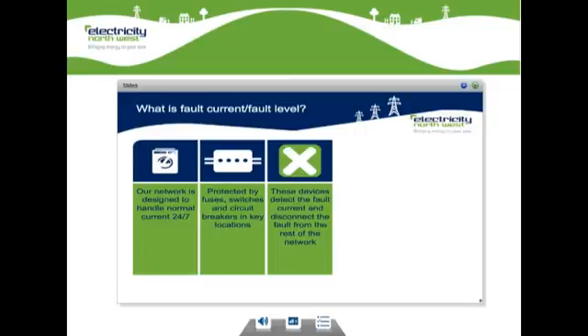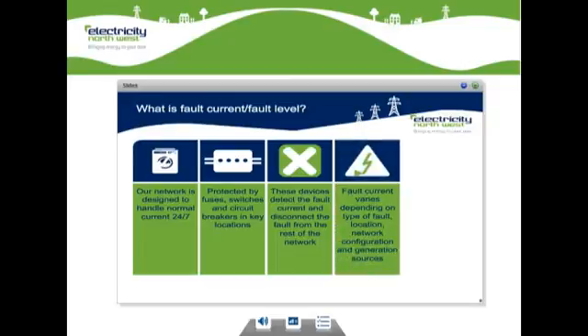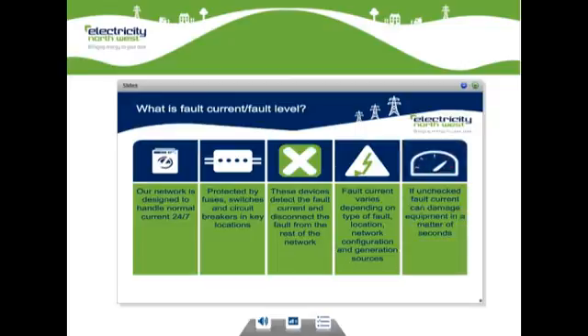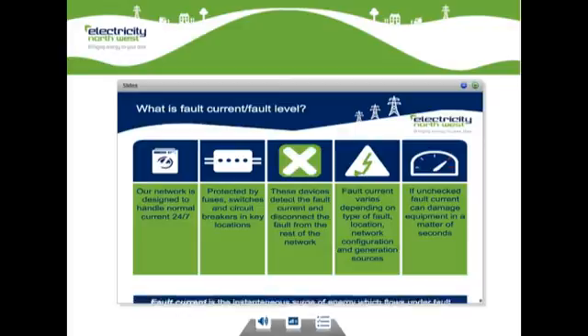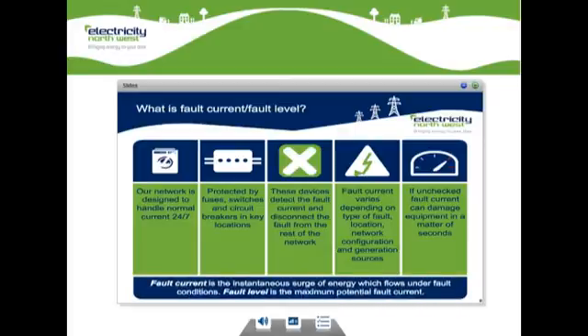The amount of fault current that flows for any fault will vary depending on the type of fault the system's experienced, the location of it, and how the network is configured at any moment in time, plus the amount of generation that's connected. If unchecked, fault current can damage equipment in a matter of seconds. The fault level is the maximum we expect this fault current to be.